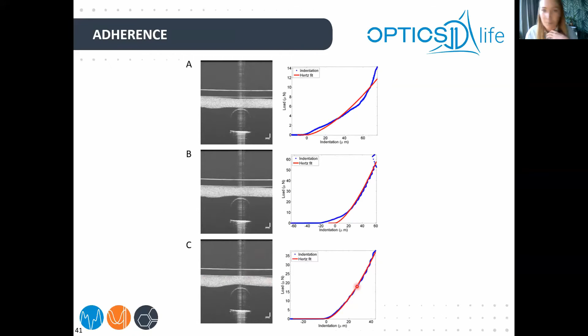Now in the second case, I had only a very small gap, you can barely see it. Even in that case, if you do the same, first you have one slope and then a higher slope. The first slope is just pushing the sample towards the glass. And then once it gets in contact with the glass, you have a proper curve. And finally, of course, if you have a nice mounting of a sample, your Hertz curve looks perfect. So it kind of gives an indication. So sample mounting is very important. It shouldn't be floating.